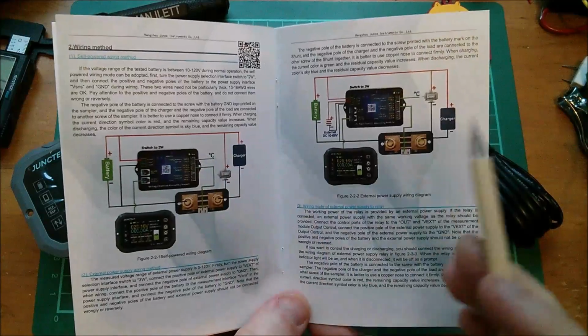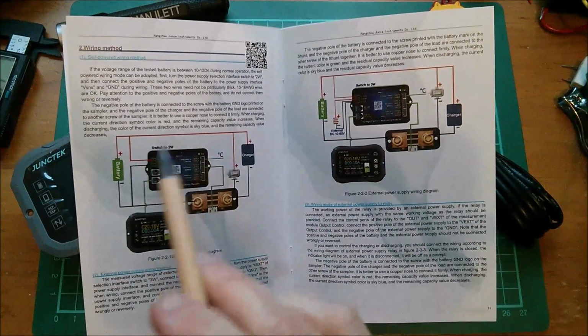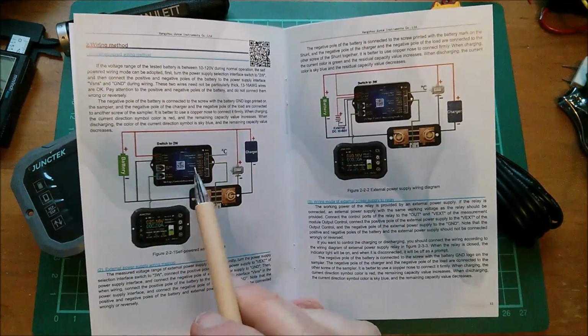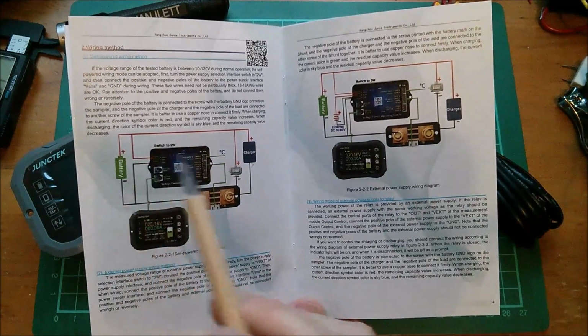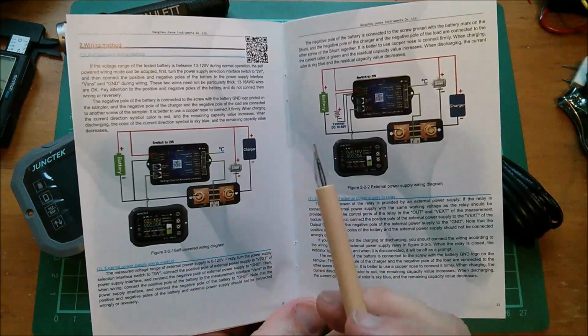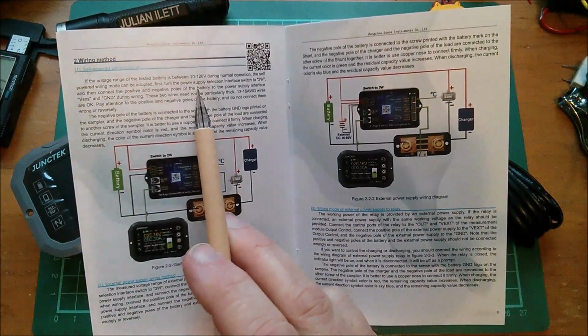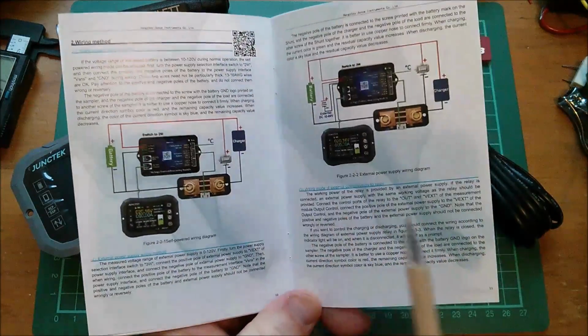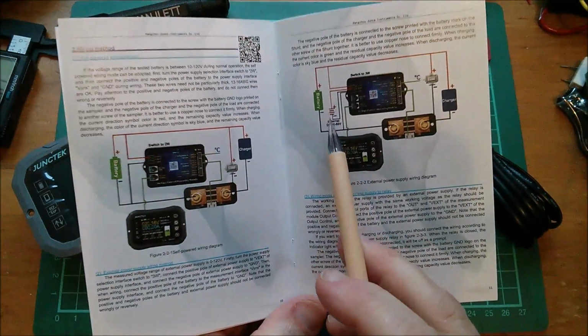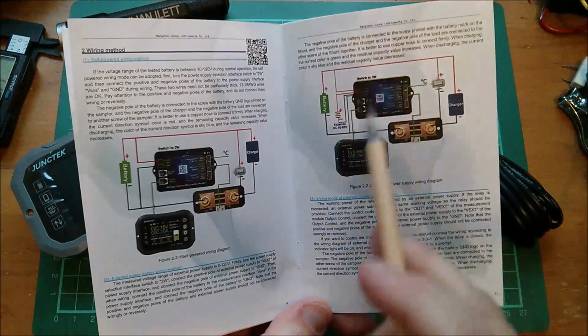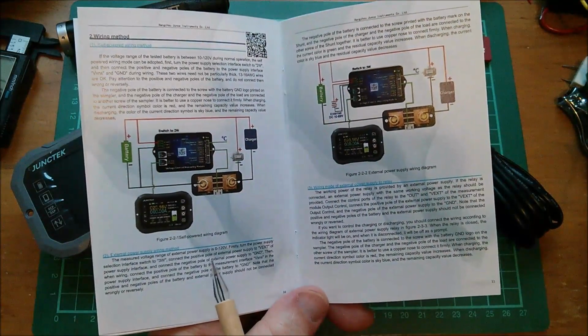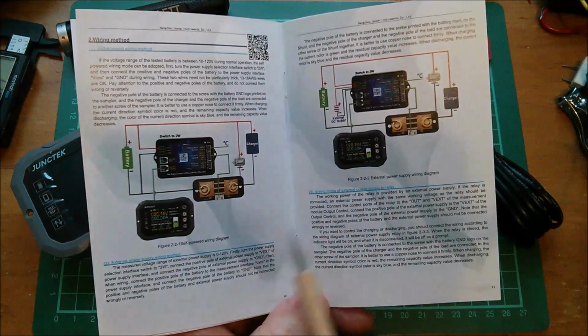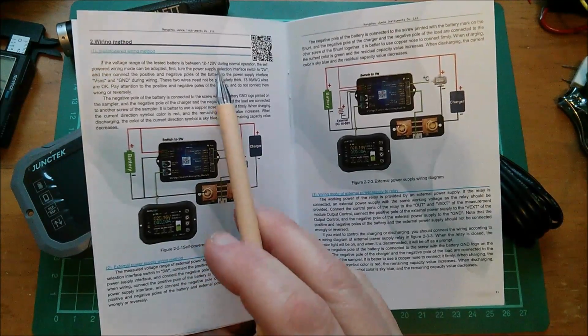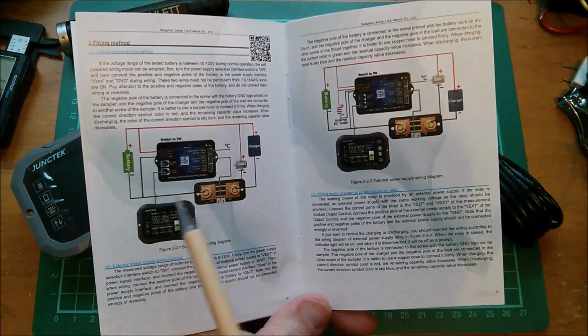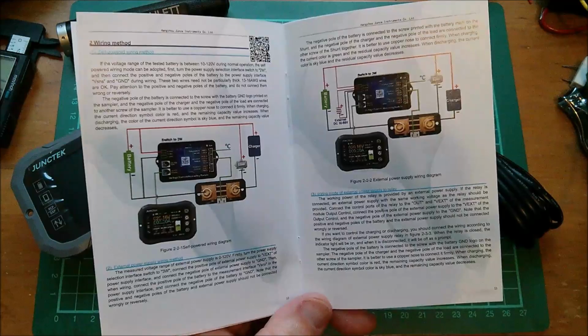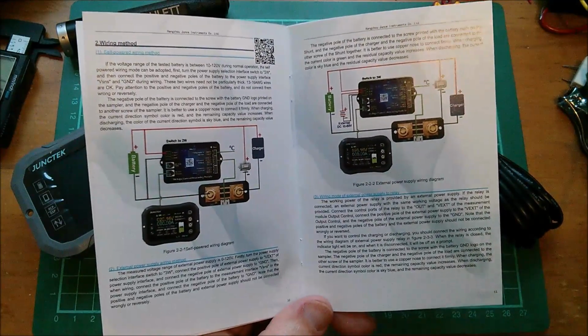So in the manual, there are two wiring modes. There's self-powered mode, where the electronics box is powered from the battery you're measuring - that means you've got to have a supply of between 10 and 120 volts. Or you can do external powered mode, where you have a separate battery to power this unit, and that can do 0 to 120 volts. Well, I'm quite happy with the 10 to 120 volt range, so I'll set up something that lets me do self-powered wiring mode.